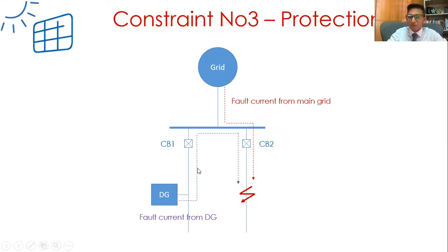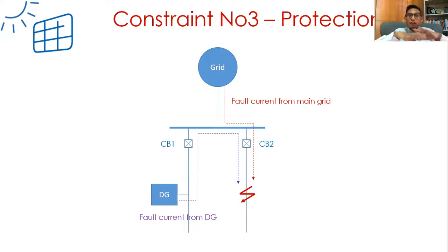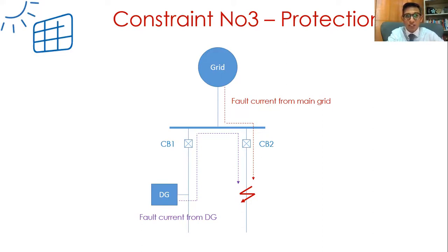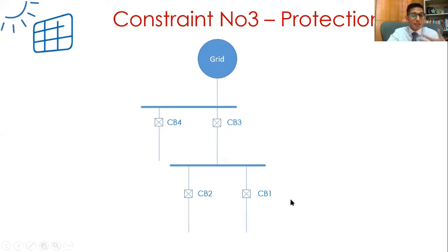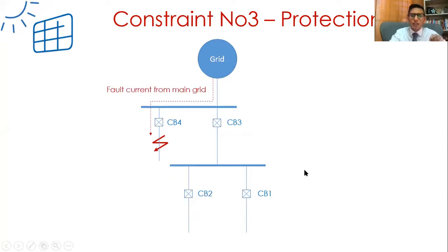What will happen to CB1? It's going to trip as well because it is sensing an overcurrent. So now with a fault downstream of CB2, both CB1 and CB2 trip - a complete blackout of the system, only because of the addition of distributed generation. We can fine-tune the protection system, but it's not easy. If you have intelligent relays, this can be done. But when you have static switch-fuse devices that can't be reprogrammed, things become difficult.